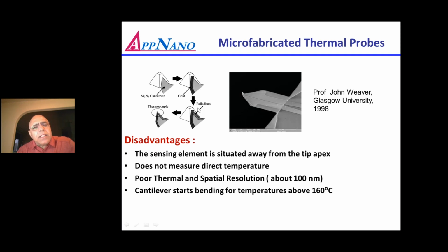The biggest thing to realize is that when you make this, the sharpness of the tip is decided by the thickness of the nitride. Secondly, the thermocouple is away from the apex. It has to be inside here, where the cursor is, a little bit down below the apex. So when you are scanning, you are scanning with the nitride tip and not the thermocouple, so it is away from that. As the scan keeps continuing, the nitride cantilever wears out, and your thermocouple is coming closer and closer. That changes any calibration you might have done before starting the experiment, because the distance from the sample to the sensor is changing. So this is another drawback here.